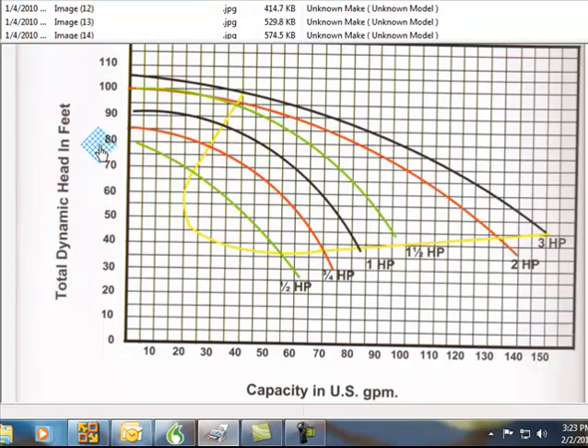But I want to go over this. And everybody gets confused. Well, Harvey, I don't have my pool pump 80 feet in the air, so my half horsepower pump is going to max out at 60 gallons a minute. No. Now, what you need to calculate, guys, and this is where it gets tricky, you have to calculate all your pipe.